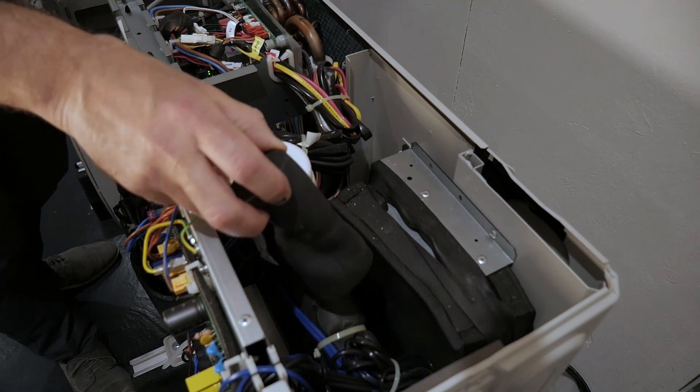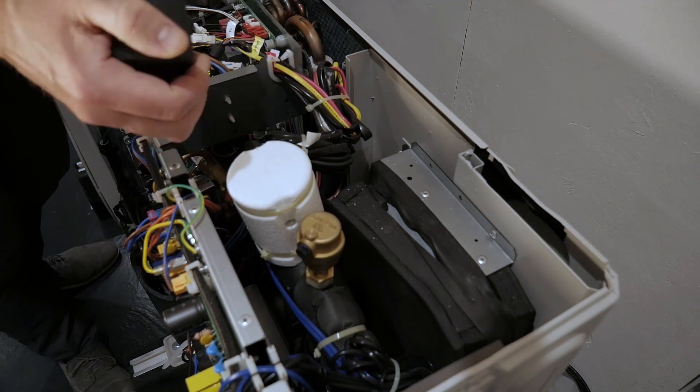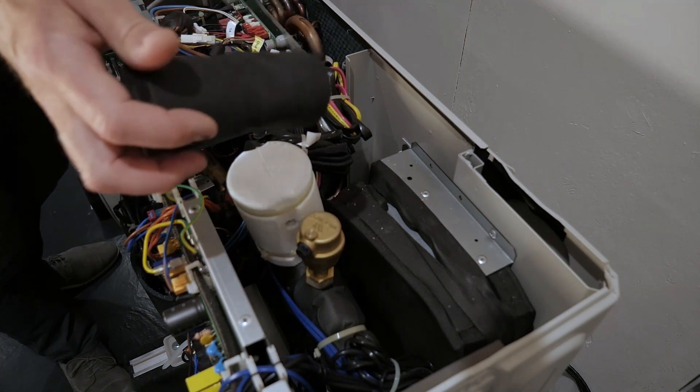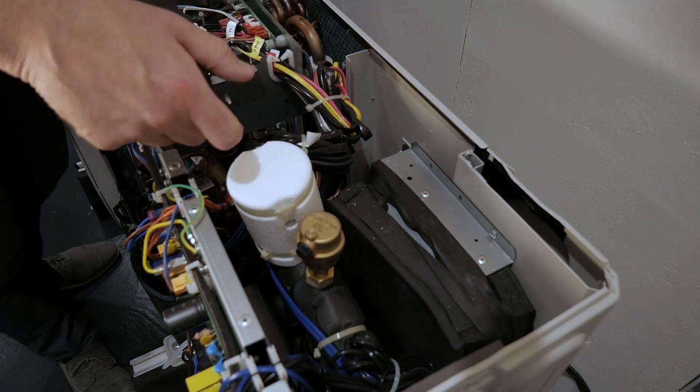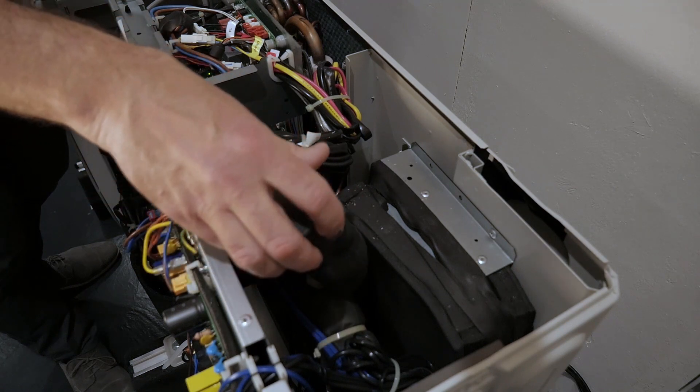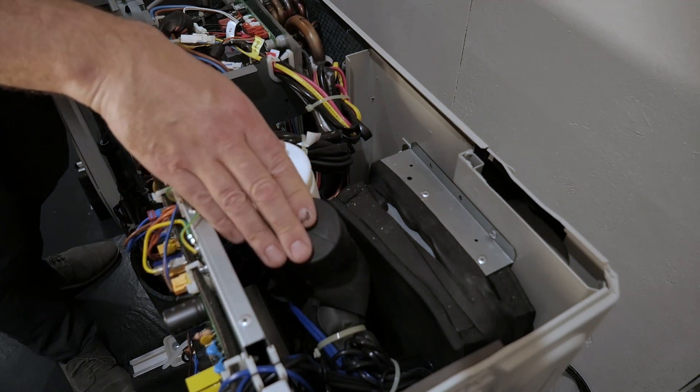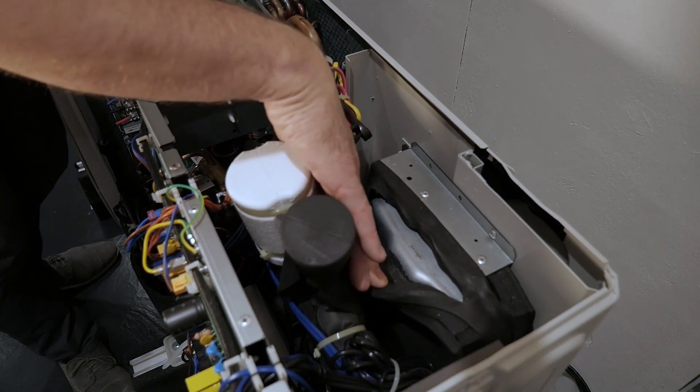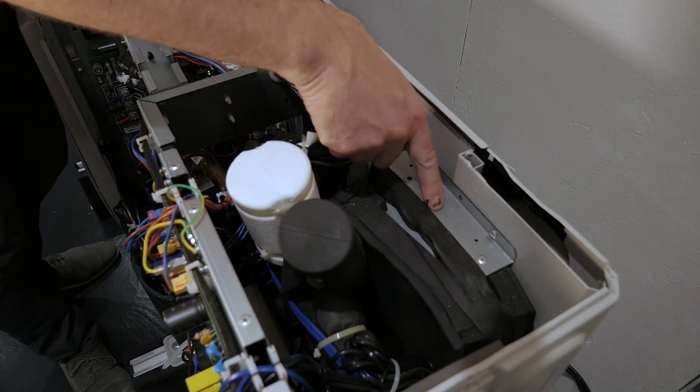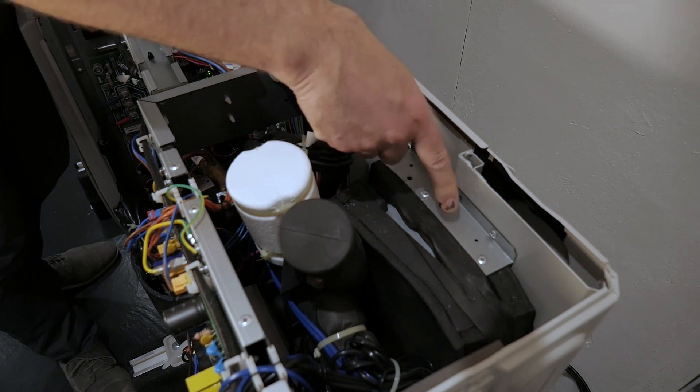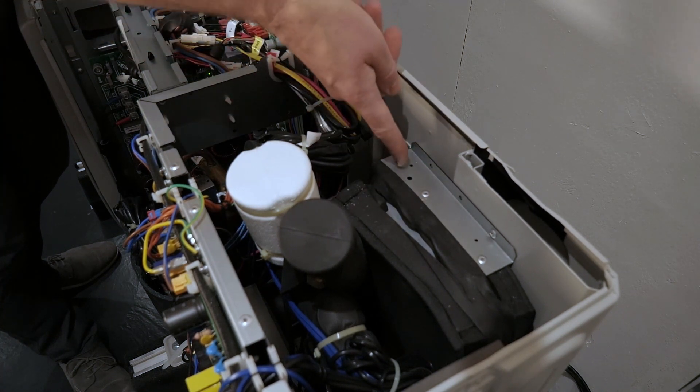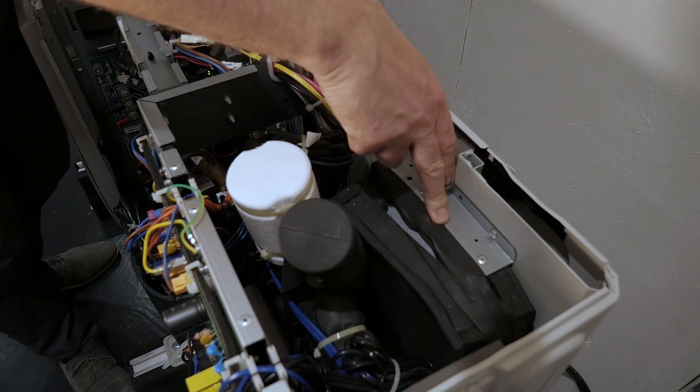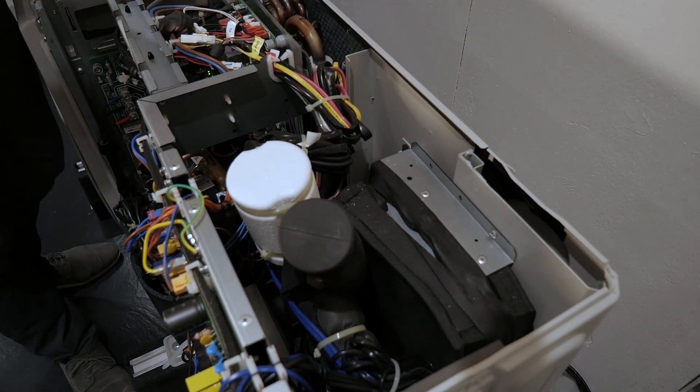Once you get the unit, you will have to actually access this little AAV here - it comes closed, so when you're filling the system you will need to open up that little AAV. There's a flow sensor under this polystyrene bit of insulation here. And this is where your expansion vessel is sat underneath this insulation here. It does have the schrader valve to detect the pressures, but unfortunately it is behind this bracket, so you will need to undo this metal bracket to get to the schrader valve to check your static pressure on that.